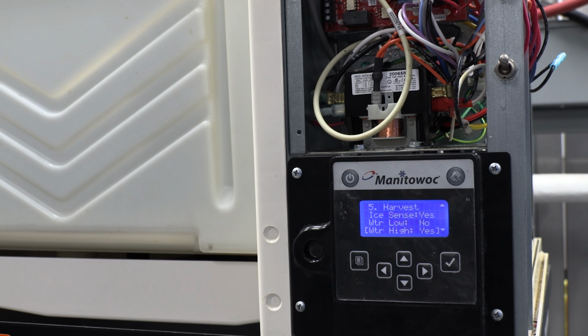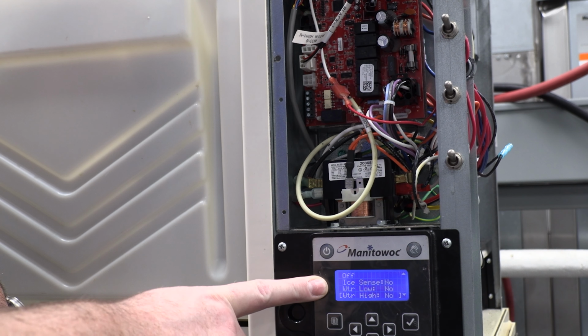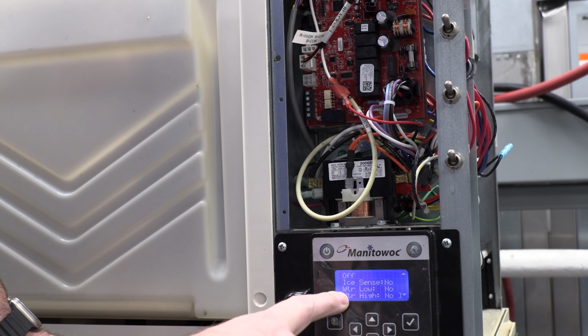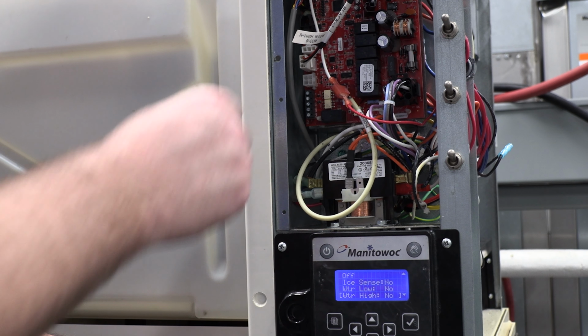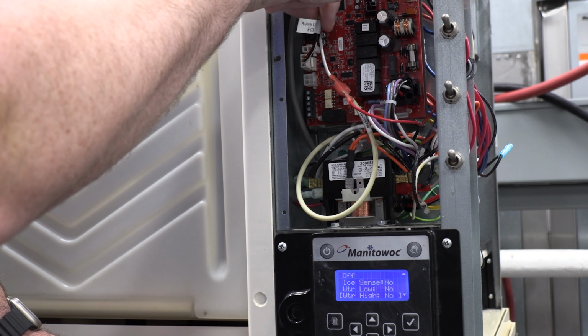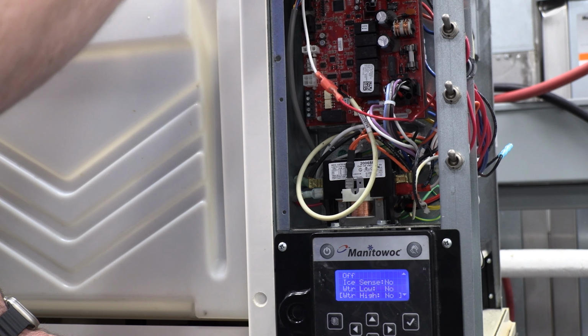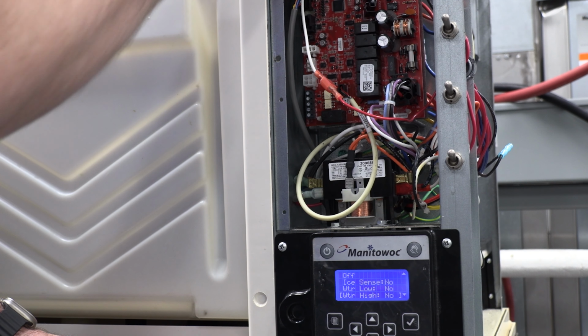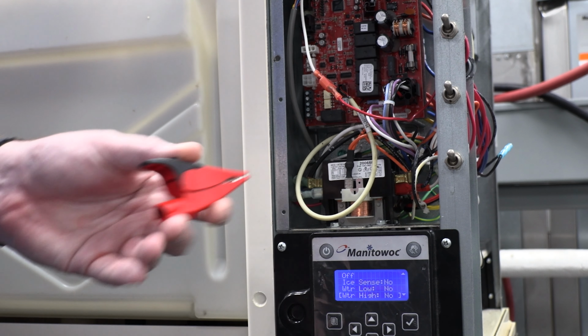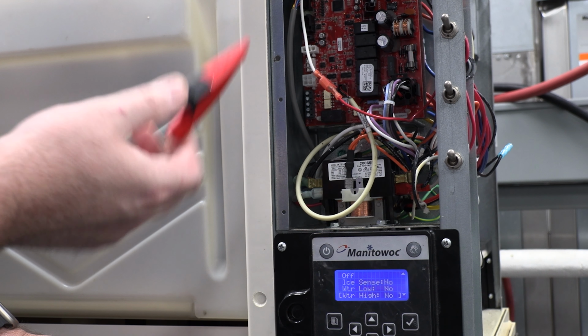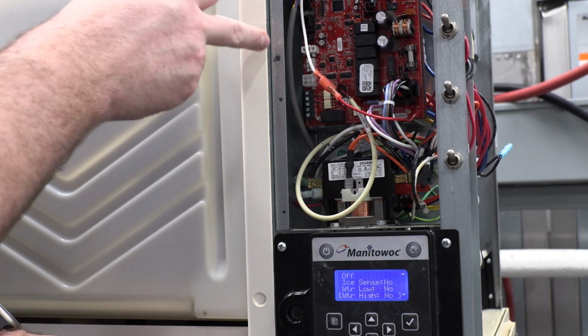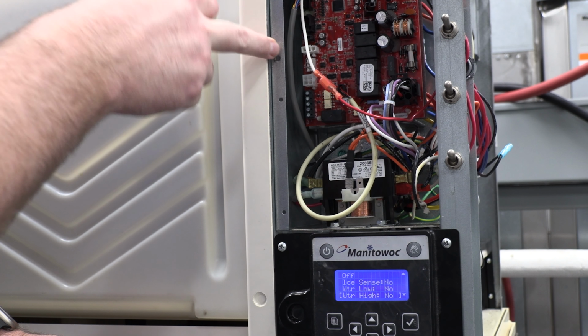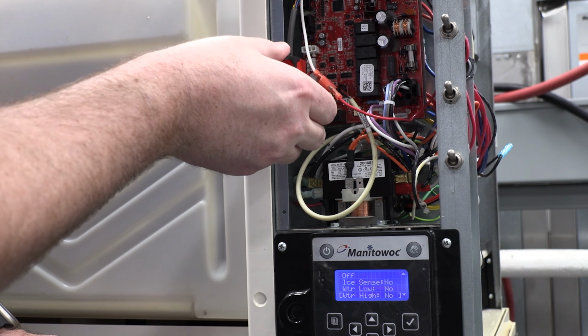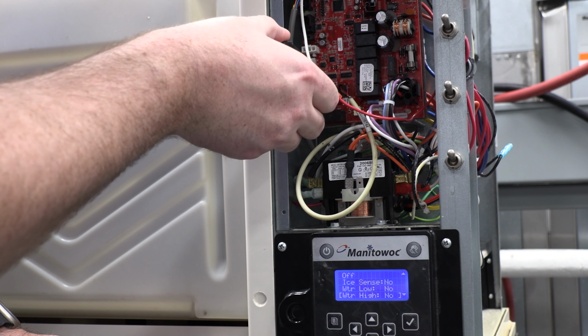I'm going to now show you how to test the input side of the control board so you can determine if it's a control board or a probe issue. We're going to be in the same real-time data input screen. We're monitoring water low and water high. This 3-pin wire connector right here is your water level harness. You can go ahead and unplug that and put that up out of the way. I like to use my jumper lead off of my multimeter lead in order to jumper these two out. You'll see the 3 pins are labeled. You have an H for high, a C for common, and an L for low water level. We'll start with just jumpering the common to the low pin.